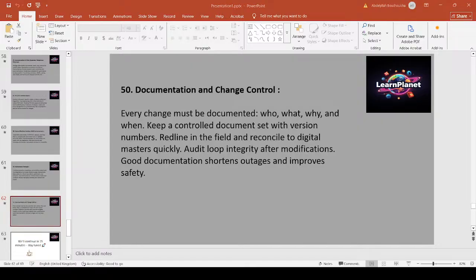Document every change: who, what, why, when, and maintain version control for datasheets, logic, and P&IDs. Redline field changes and reconcile with electronic masters quickly. Delays lead to bad decisions and miswiring in later phases. Audit loop integrity after modifications, and perform regression testing for safety-related changes. Example: when retuning a control loop, document parameter changes, reason, test results, and rollback plan in the change control system.